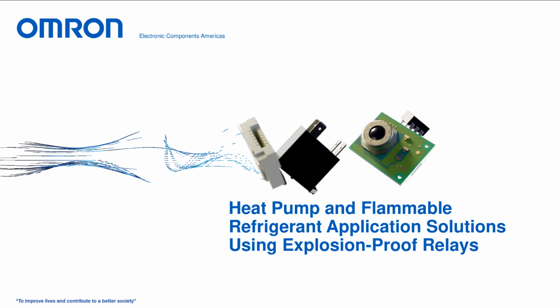And once they're certified as such, they're no longer an ignition source. This means that we've done the testing through IEC to show that we will not ignite based on switching in these flammable gas environments. So even without that full barrier and full isolation, we will not cause ignition of the flammable gases that were used within. So if there's a particular gas that you're concerned about, we can reference that particular IEC certification. But unsealed is definitely a go as long as we have the testing and the approval by IEC or UL. Okay, yeah, that's helpful.